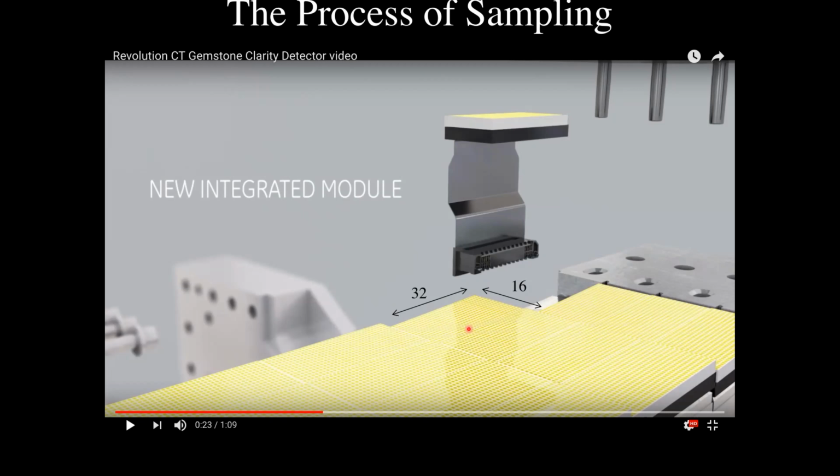Just in terms of how many X-rays you can make with your X-ray tube and how many you want to put in a patient. One manufacturer, Canon, just said, to heck with it, we're going to make a high resolution detector, and they did just that. They cut these things into 2 by 2s. And so now they have a detector which actually is twice as big. It's like 2K by 512. So that scanner actually makes higher resolution pictures.